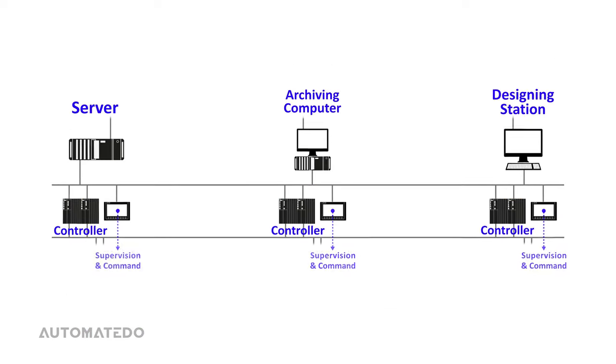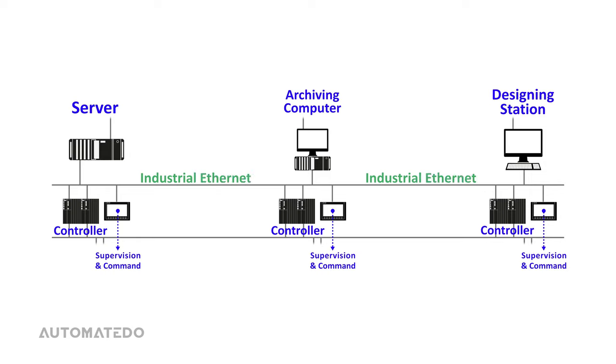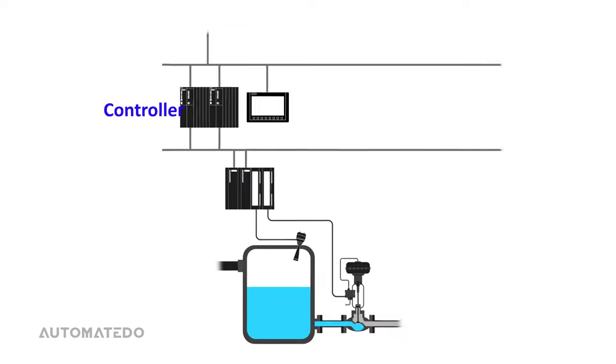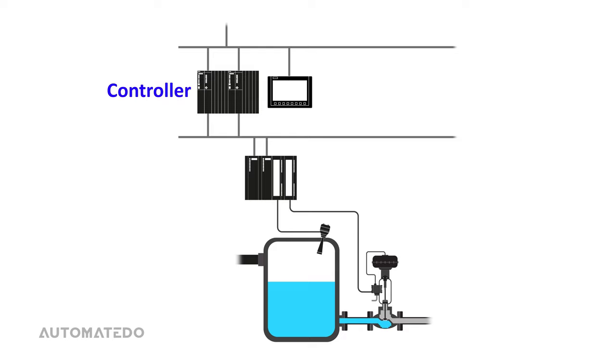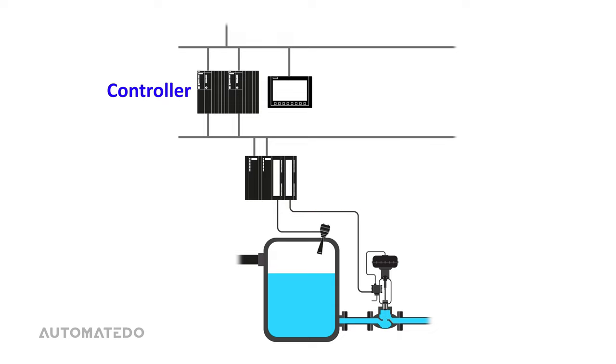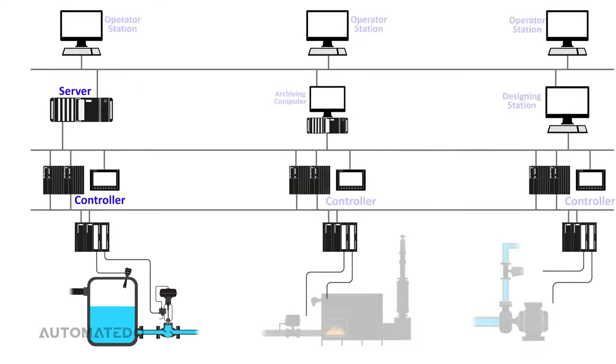We find the master controllers and supervision and command units in the next level. Commonly, we use industrial Ethernet to communicate with the previous level. Controllers or process stations are in charge of supervising and operating the separate processes. They acquire input signals measured by sensors, analyze the information based on the logic implemented, and finally generate output signals to control the actuators.